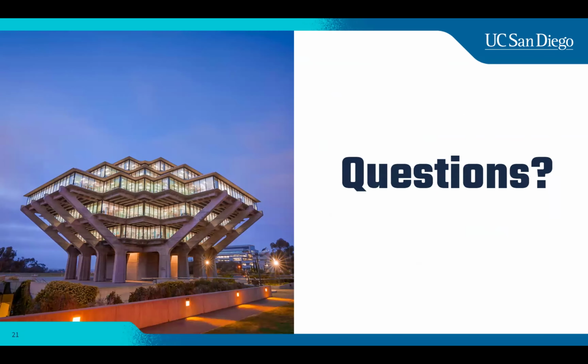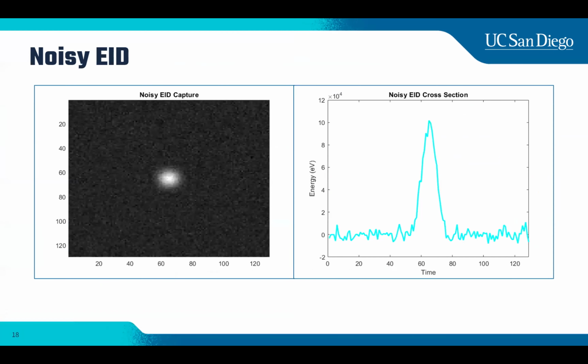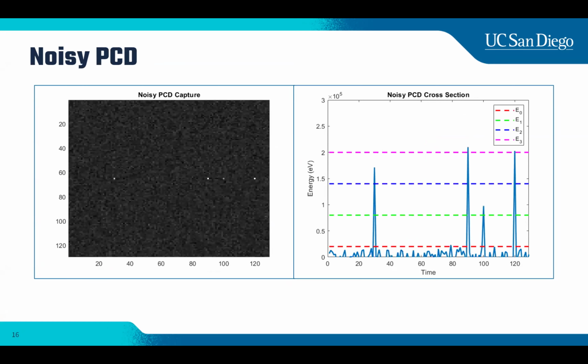All right, thanks. That's cool. Can we go back to the slice where you have the one before this, I think, and the one before this, that one. Yes. So now we're rocking along in time on the x-axis. We have one detector element, the middle one, 64, which is giving photons of different energies. That's right. Okay, the noise baseline there that you've got is from electronics in the whole system, and you've eliminated that noise just using the threshold of an energy bin, right?